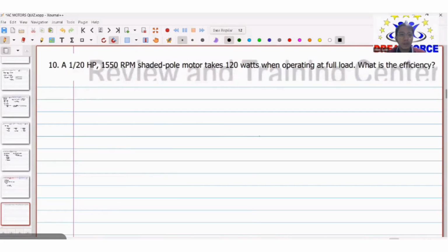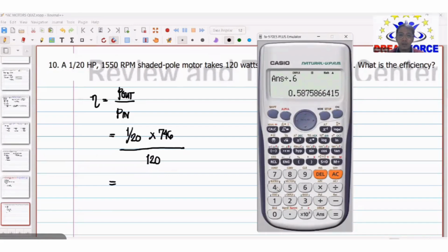So a 1 over 20 HP, 1,550 RPM shaded pole motor takes 120 watts when operating at full load. What is its efficiency? Sabi natin, efficiency is the ratio of the output power over your input power. So what is our output power? Ito na po siya. Your output power is 1 over 20 HP times 746. So yung input natin, the motor takes 120. That is in watts. So that is simply 746 over 120 times 20.